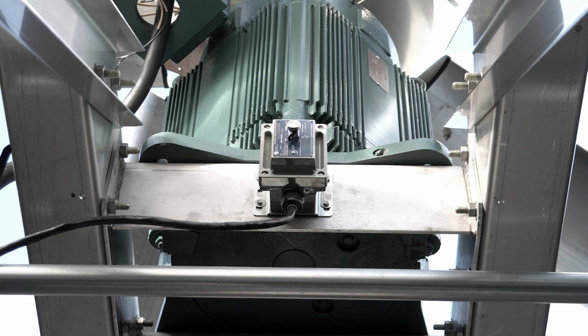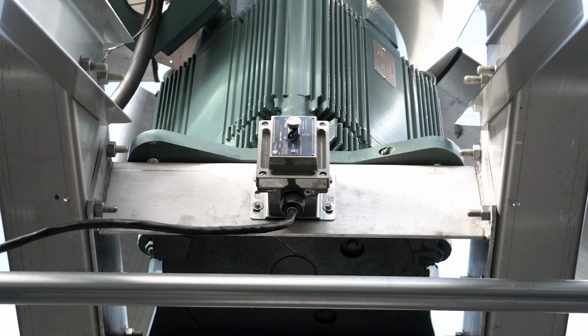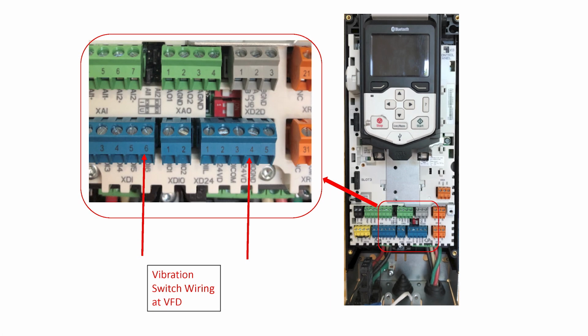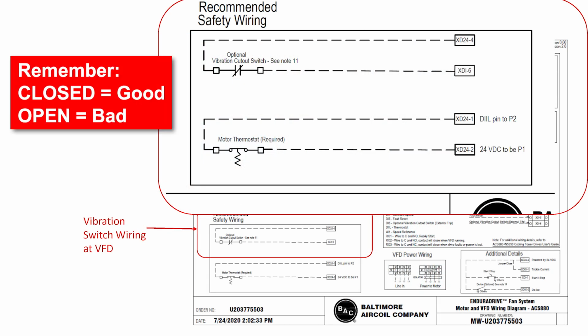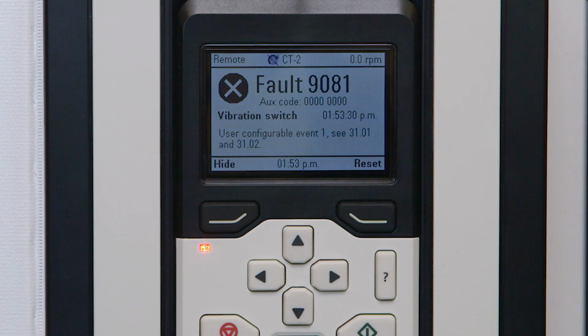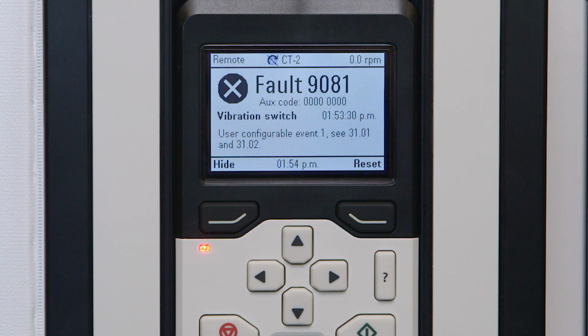Vibration switch wiring. Now that we are sure the thermostat is correctly wired, let's do the same for the optional vibration switch. If you do not have the optional vibration switch, skip this step. If you are using a tower vibration switch, make sure it is correctly wired to the VFD terminals. The vibration switch wires should be connected to XDI6, which is labeled DI6, and XD24-4, which you see labeled plus 24VD as pictured here. If the vibration switch is not correctly wired, there will be a fault message on the display that reads Vibration Switch.